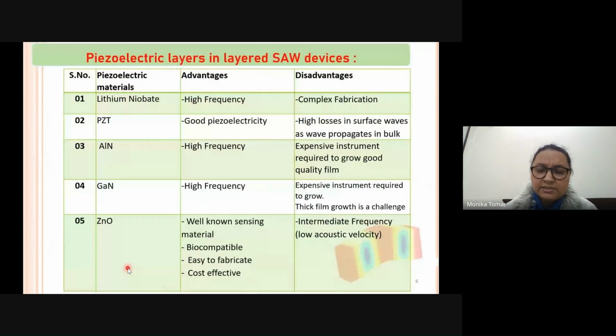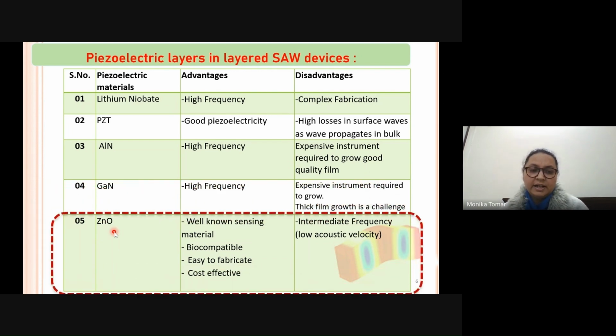Amongst the piezoelectric layers used in SAW devices, there are lithium niobate, PZT, aluminum nitride, gallium nitride, and zinc oxide. All of them have their own advantages and disadvantages. Amongst them, we prefer zinc oxide because it is a very good sensing material because of its absorption and desorption properties. It is biocompatible also. We can easily fabricate it using a number of techniques, and it is cost effective. But the challenge is that we can use it for the intermediate frequency regions only because of its low acoustic velocity. However, we are working towards increasing the velocity by lithographic capabilities and by using a layered structure, where we can use a substrate with higher acoustic velocity, and then the overall frequency of operation of the device can be enhanced.